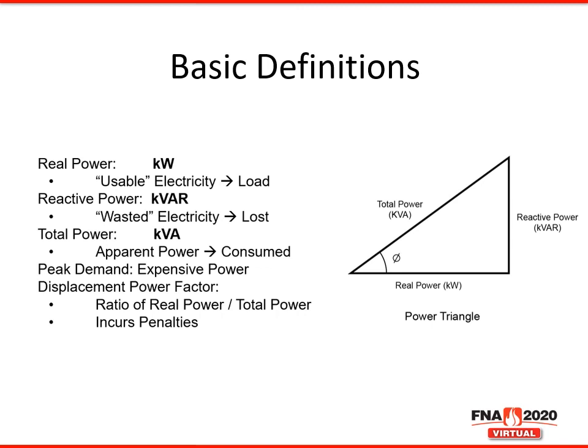Before I get into the results of the case study, I want to go over some basic definitions of power. Real power, or kilowatts, is usable electricity. Reactive power, or kVAR, is wasted electricity. On the right here, you can see the power triangle. Real power is on the bottom and is 90 degrees out of phase from the reactive power, or kVAR, on the right. The angle that this triangle forms is known as the displacement power factor. I'm going to get into this more later, but it is essentially how the current can lag from the applied voltage.